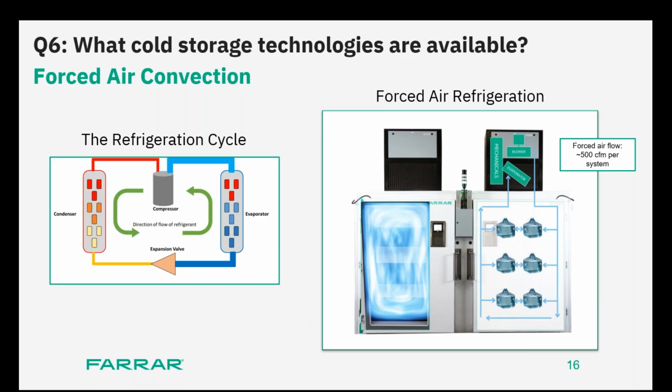Think about it. With standard ULTs, oftentimes when the ice buildup is so severe, you'd have to unplug the freezer at least twice a year. And during that time, you have to worry about a secondary unit to transfer samples. Needless to mention, that phenomenon, which is something everybody likes to avoid, is known as the transient warming event, TWE.